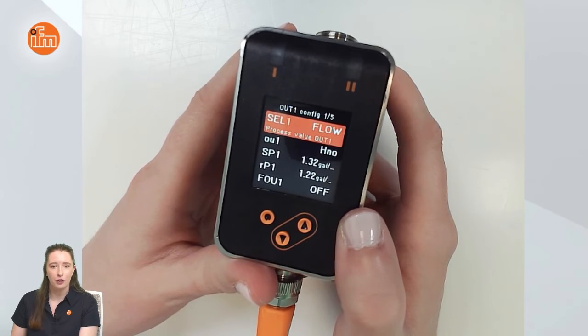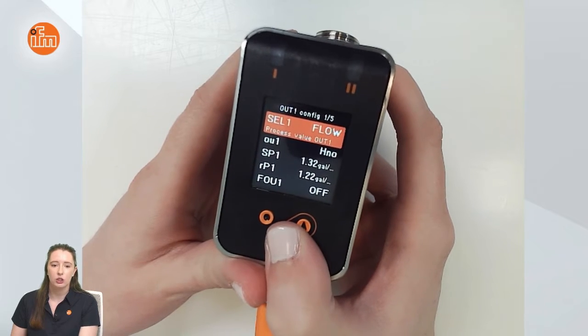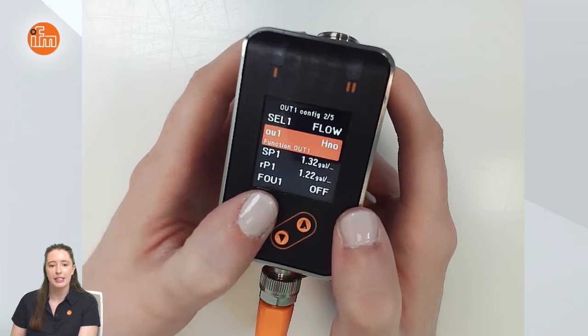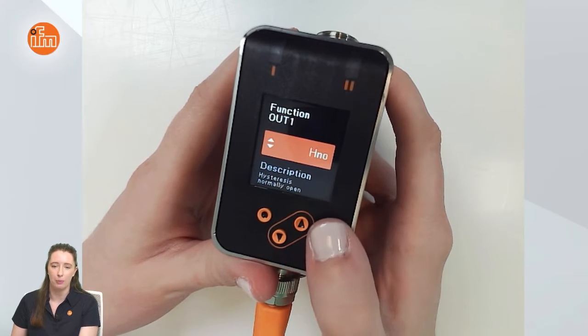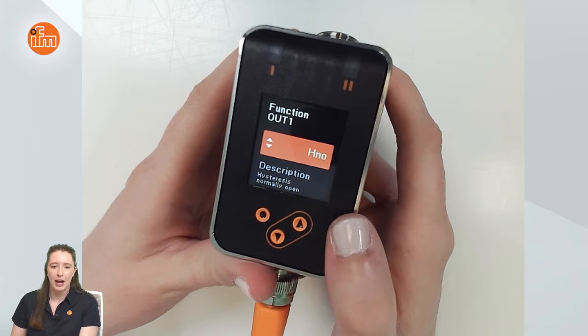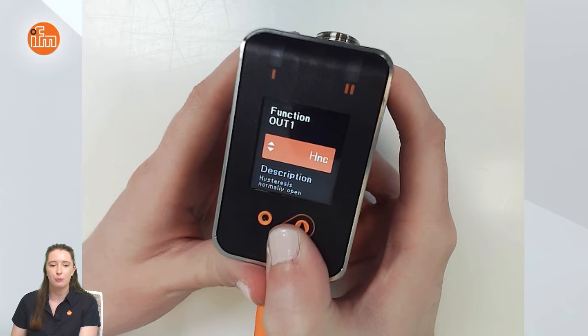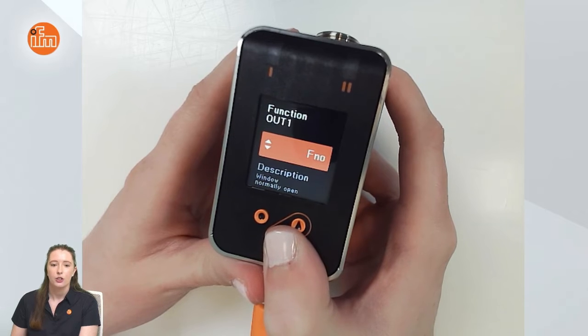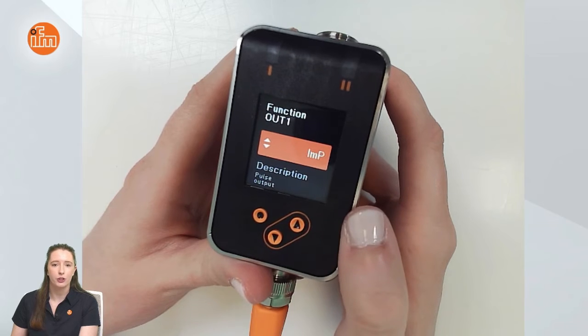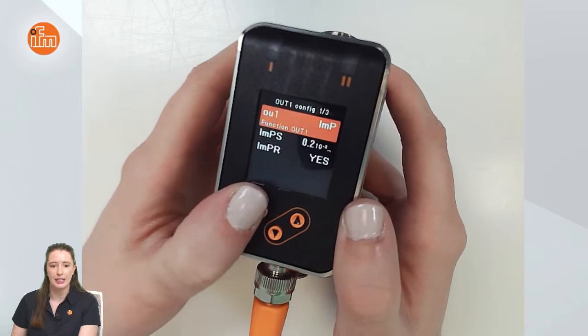SEL one is already set for flow, which is what we need to set output one for a totalizer output, so we just need to go to out one and press enter. Here it is set for Hno, which is a hysteresis normally open output. Press either the up or down arrow key and hold it — you'll see the bar load and then you can toggle through your output one parameter settings. To set it for totalizer you need to set output one to impulse ImP and press enter.